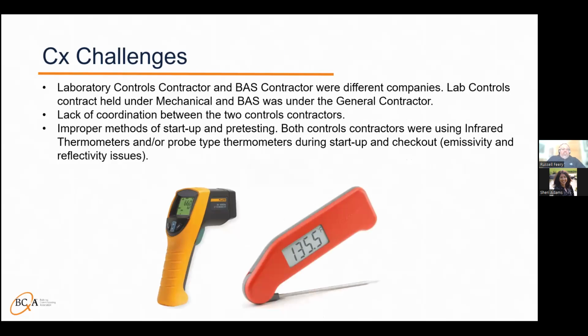Some of the commissioning challenges that we found on the projects is that the laboratory controls contractor and the BAS contractor were different companies. Further compounded, the lab controls contract was held under the mechanical and the BAS was under the general. That led to a lack of coordination between the controls contractors and somebody that ultimately had the responsibility for providing a system that was functioning and pre-tested. We've also found that during startup and the issues that were identified, we started asking the controls contractor how they did startup, and many of them used a traditional probe type sensor or even an infrared gun, and neither one of those are accurate for properly testing chilled beams.